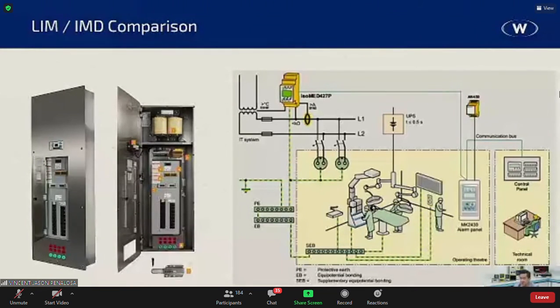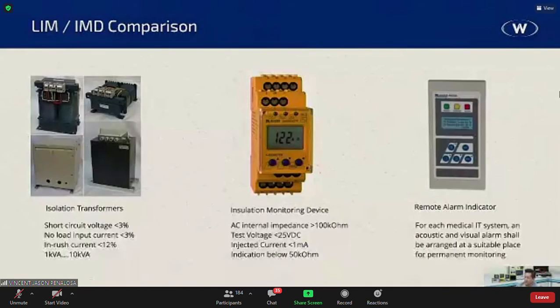So again, you can start installing that transformer outside of the operating theater, and you have a control panel going towards the maintenance guys or the nurses station or wherever. Now, this is the kind of system that you will need if you are going to have an IEC compliant system for your operating theater. You will have your isolation transformers, again no more than 10 kVA, 1 kVA to 10 kVA. There are specific isolation transformers for OR lighting that are separate from the operating theater system. Then you will have your insulation monitoring device. Again, the injected current is less than 1 milliamp, and the indication will be below 50 kilo ohms, as compared to the regular ones, which is 40 kilo ohms and 10 kilo ohms.